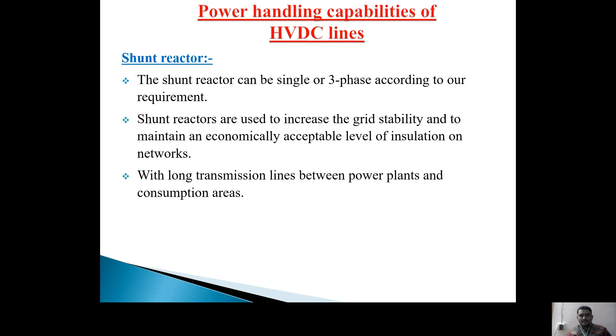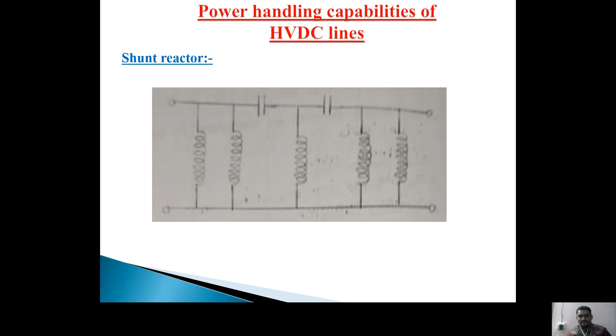This is the diagrammatic representation of shunt reactors. Here I am taking a transmission line which comprises capacitors and shunt reactors. Coming to the features of the shunt reactor: it maintains acceptable voltage at the load, limits transient over voltages induced by switching load decreases, and decreases the line losses by capacitive current reduction.